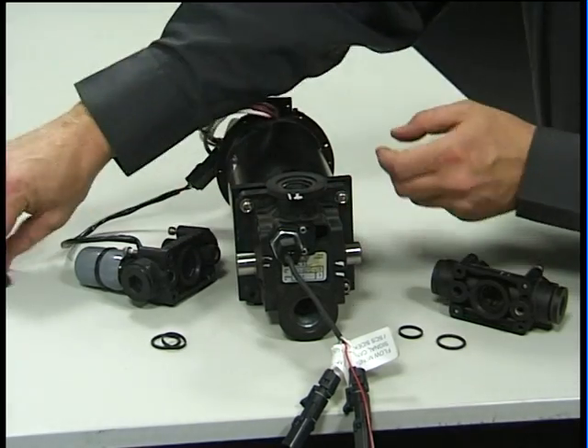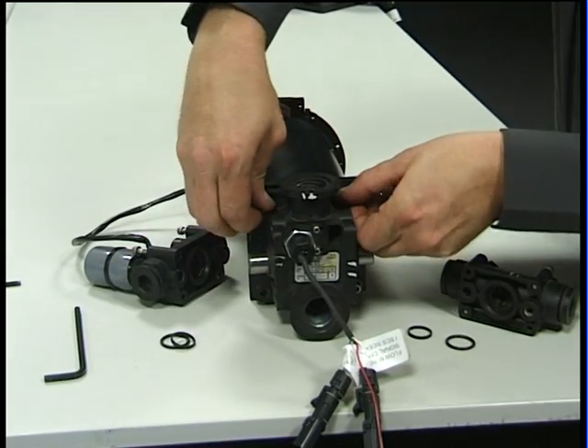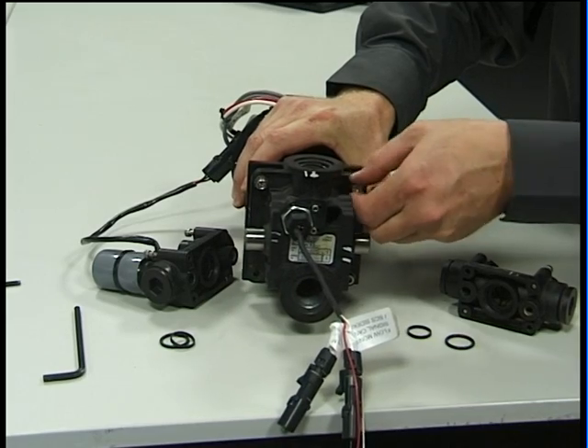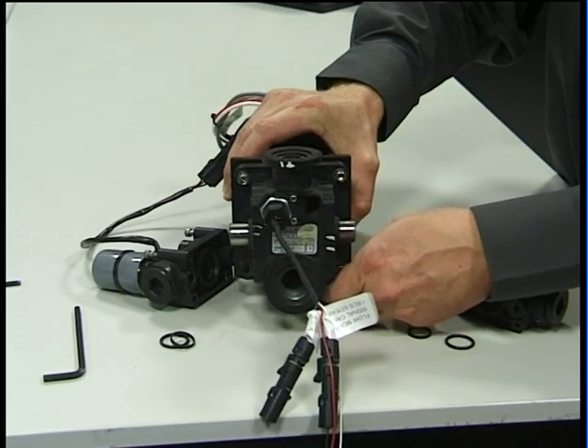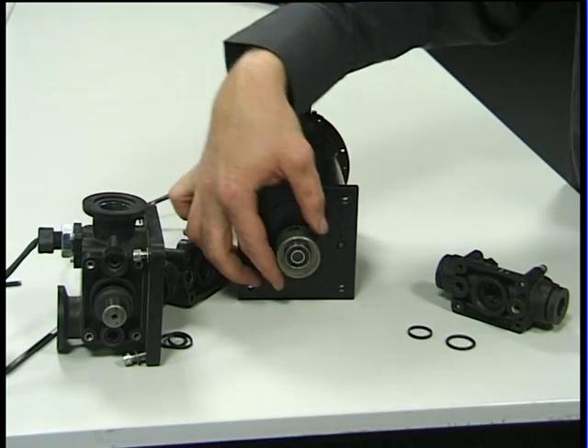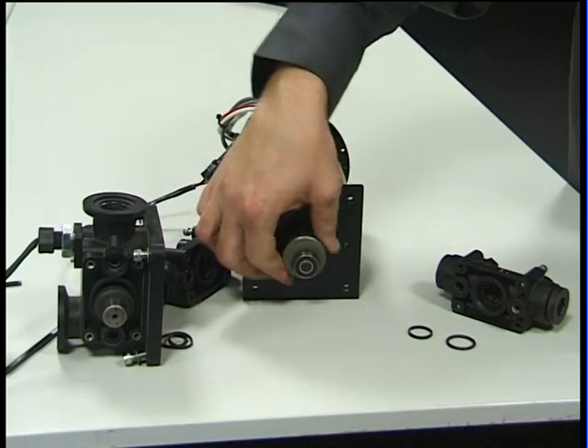To remove the main pumping element, use the right size Allen key and remove the pumping element. There is a cam connected to the motor which turns and moves the plunger backwards and forth on a ball bearing to create the pumping.